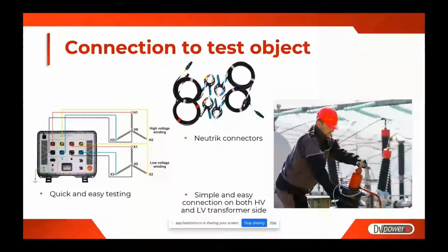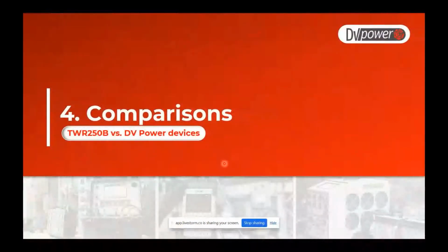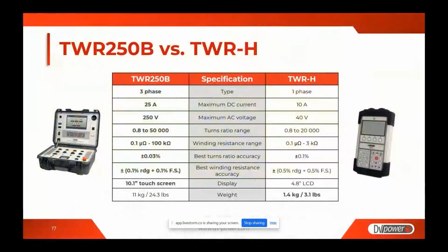And now quickly I will compare the new device with previous solutions from DV Power, where you can see our improvement. So at this slide, you can see clear advantage of the left columns over the right column. It's really not fair comparison, but TWRH was our only solution which was able to test both winding resistance and turn ratio test.